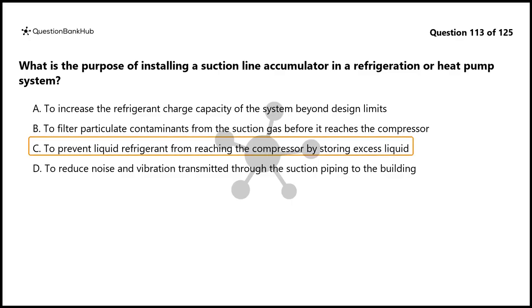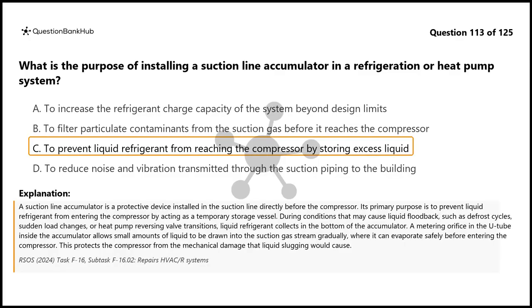The correct answer is C. A suction line accumulator is a protective device installed in the suction line directly before the compressor. Its primary purpose is to prevent liquid refrigerant from entering the compressor by acting as a temporary storage vessel. During conditions that may cause liquid floodback, such as defrost cycles, sudden load changes, or heat pump reversing valve transitions, liquid refrigerant collects in the bottom of the accumulator. A metering orifice in the U-tube inside the accumulator allows small amounts of liquid to be drawn into the suction gas stream gradually, where it can evaporate safely before entering the compressor. This protects the compressor from the mechanical damage that liquid slugging would cause.